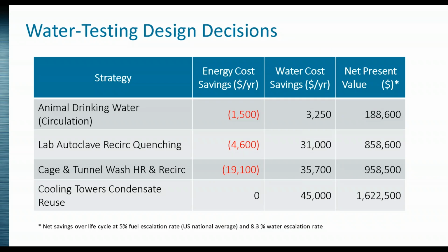What's interesting is that in the past we always saw water as relatively inexpensive, so we'd do energy accounting but not water accounting, not taking the water utility into account. But with rising water rates, in some cases if we just looked at energy, it's a penalty—we're not going to take that approach. If we take water costs into account too and look at it holistically, we start making different decisions. In some cases this extends to air-cooled chillers instead of water-cooled chillers, and other types of equipment, because of this. It's very localized—you have to understand the energy rates and water rates of that particular climate and locality, but we're seeing it's changing how building design decisions are made.